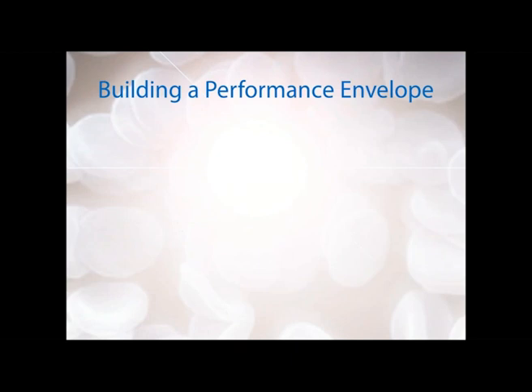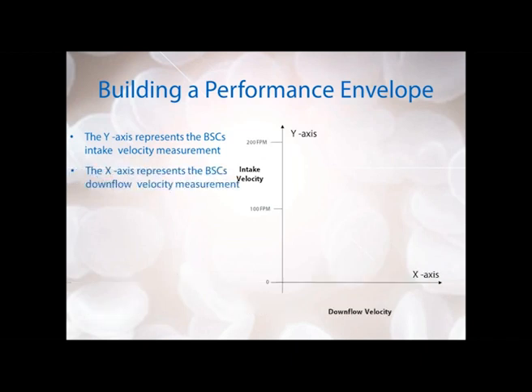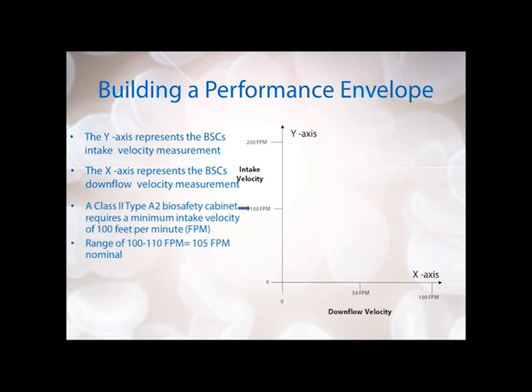We're going to use those two aspects to build our performance envelope. On the y-axis of this graph we'll plot our intake velocity, and on the x-axis we'll plot the downflow velocity. A Class 2 A2 biosafety cabinet requires a minimum intake velocity of 100 feet per minute, per NSF Standard 49. Due to the restrictions of instrumentation used to measure airflow velocity, there's a variance range of about 5 feet per minute. To ensure you never go below 100 feet per minute, the nominal set point of the intake velocity is often set at 105 feet per minute.